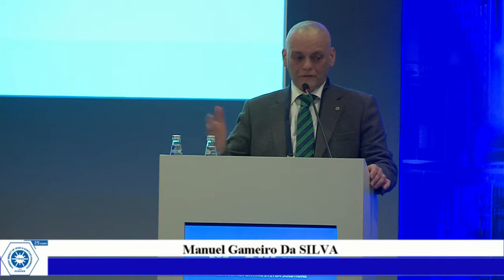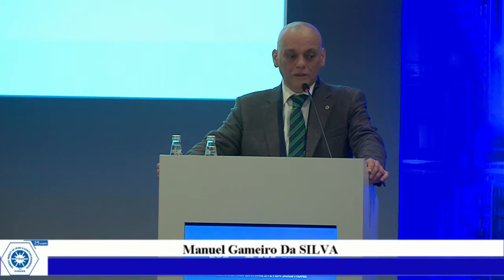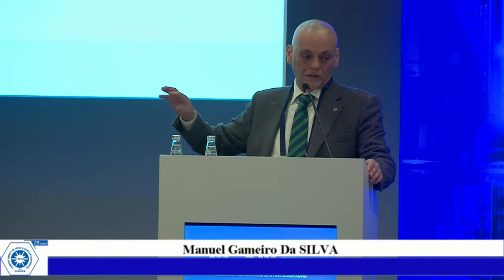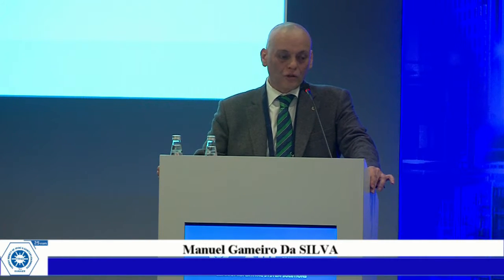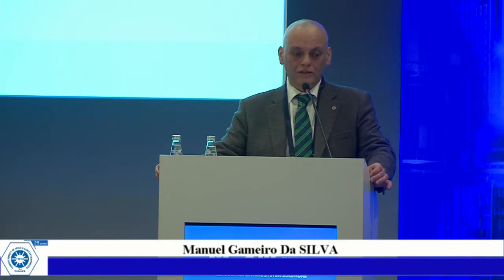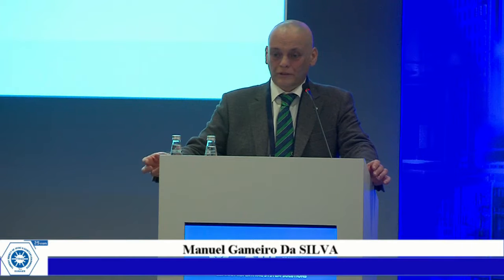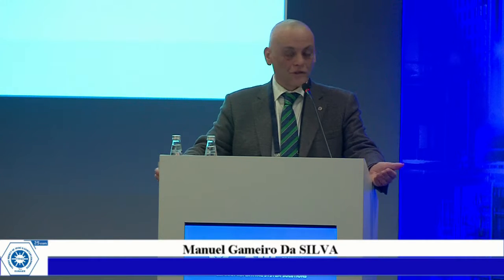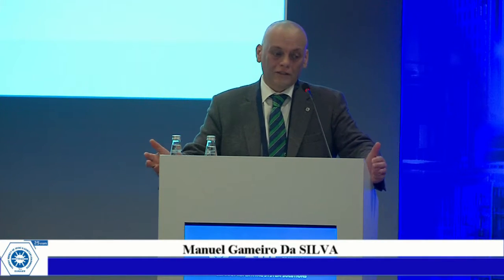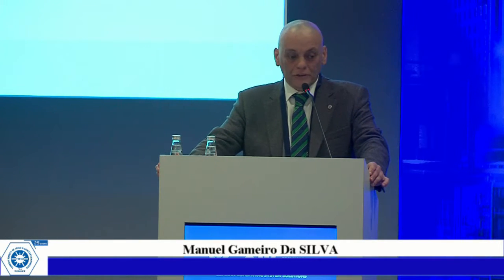So here you have along the year the breakdown between the electrical energy, which is in green, and this is somehow constant along the year. We have the district cooling in blue and the district heating, and as you see, the cooling needs of the building are much higher than the heating needs, because of course we have the internal loads, and the climate in Lisbon is somehow moderate.